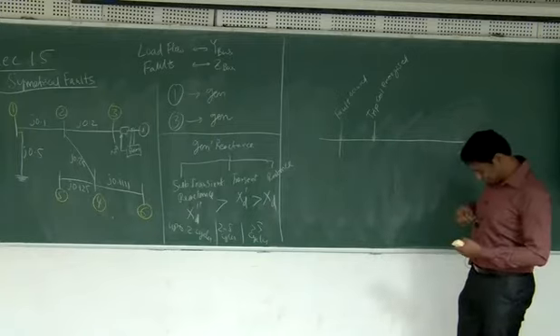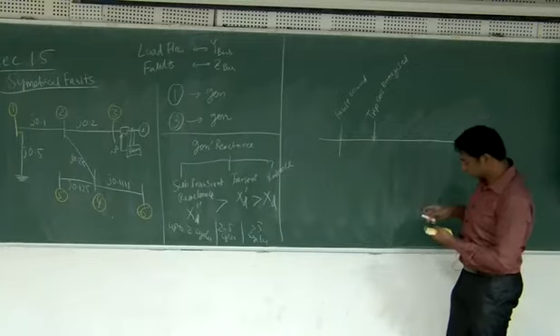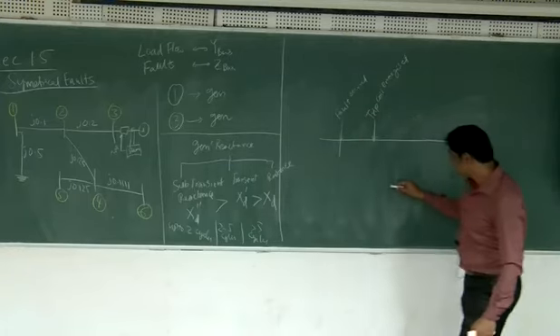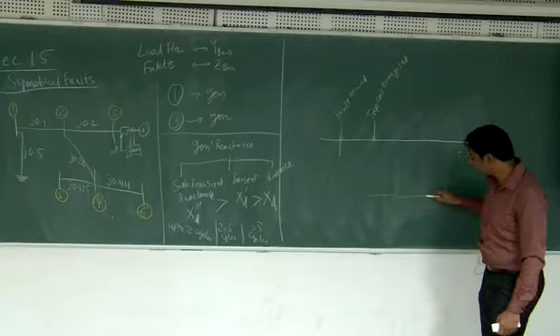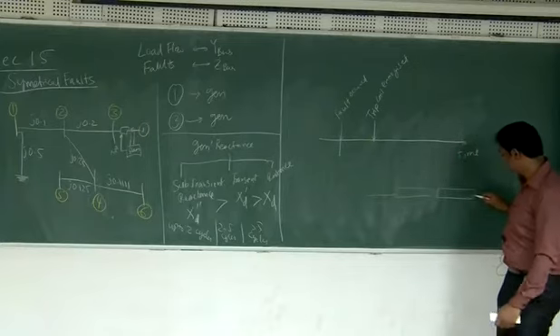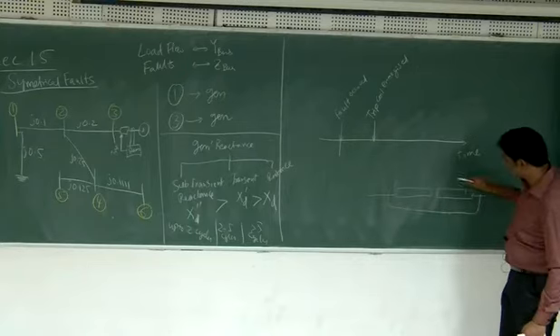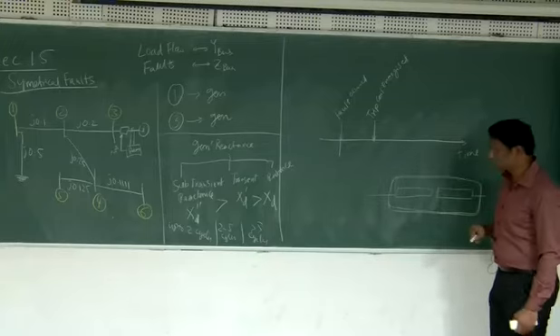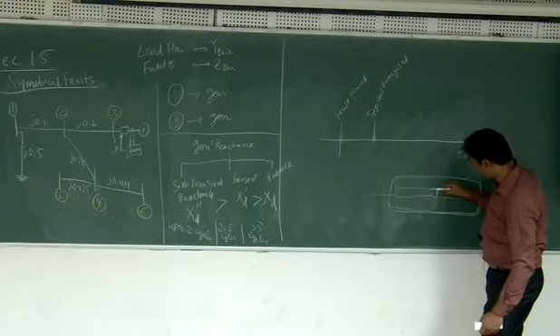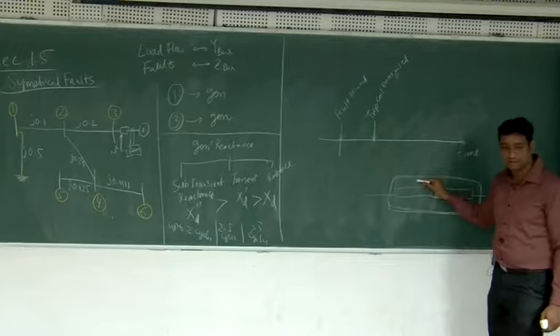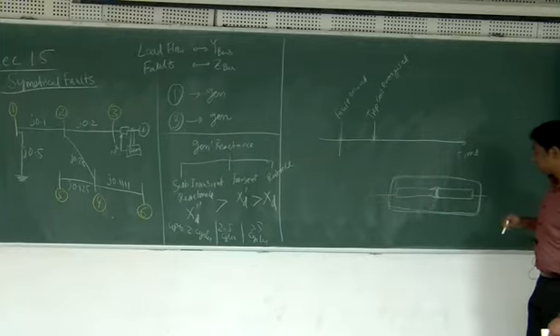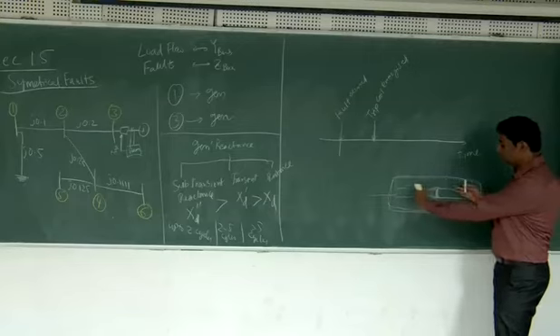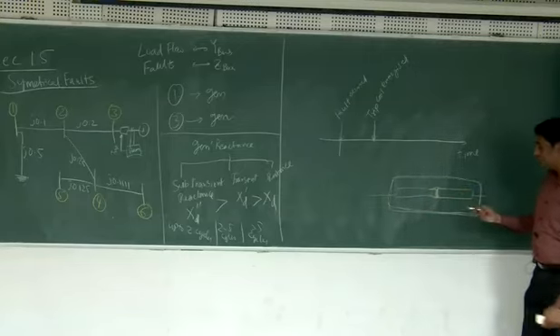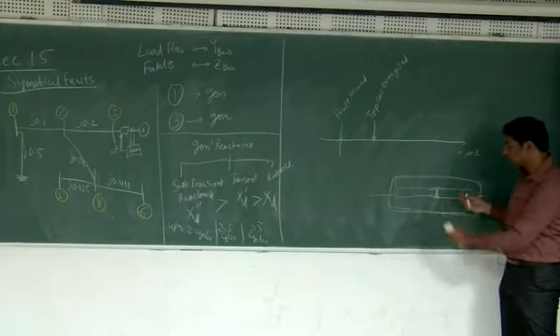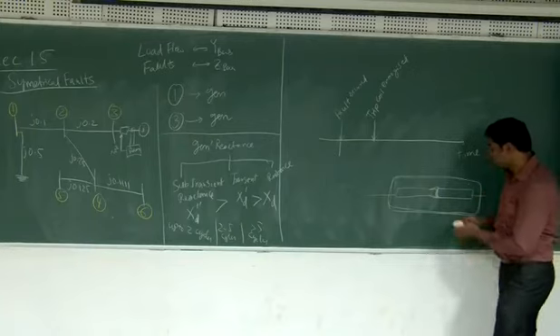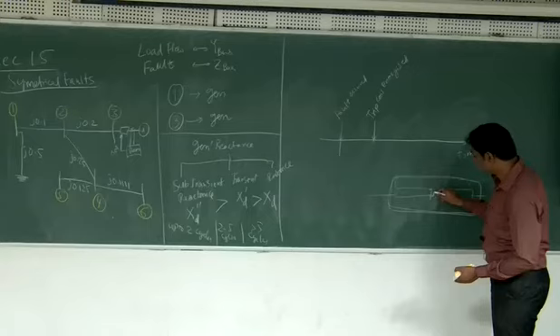So after the trip coil is energized, if you look at the circuit breaker, it will be something like this. This is the line, and then there will be mechanical contacts like this, and this whole thing will be inside one enclosure. Okay, and these two can be moved. Normally they are in contact like this, and in between there is oil or some SF6 gas or something like that. When the trip signal is received, it will separate the contacts. Whenever you disconnect any electrical connection, first you will get some spark or arc. So this is an arc.